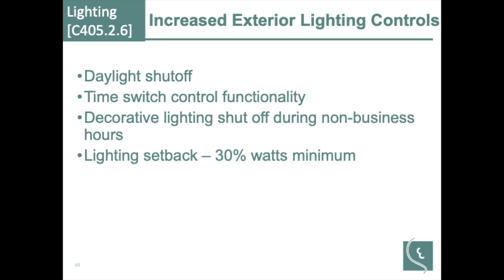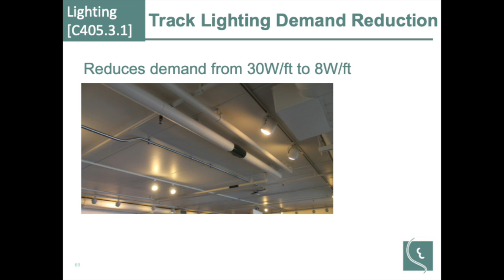Track lighting for your load calcs. They reduce the estimated load, or the minimum load for track lighting calculations, from 30 watts per foot to 8, since you're trying to put 30 watts of LED on and not overlight that room like crazy. So now it's 8 watts per foot as the minimum calculation, or whatever is installed, whichever one is higher. That compares to the National Electrical Code, which is a 75 watts per foot allowance. ASHRAE 90.1 still has it at 30. This is only IECC that changed to 8.